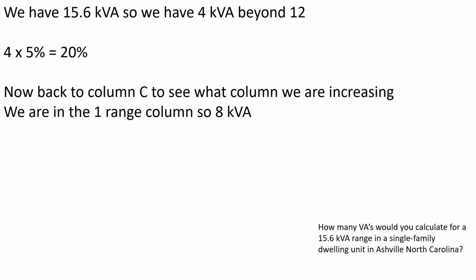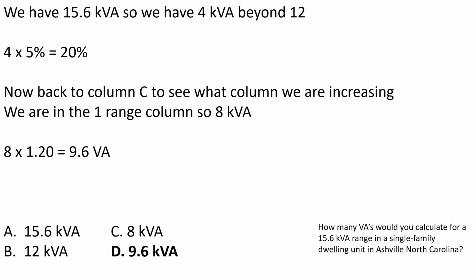Now we go back to column C to check what we are increasing. In this case, it's one range. So in column C, one range is good for 8 kVA. Then we just increase it by multiplying 8 by 1.20. That's going to give us 9.6 kVA. And we're going to select D.